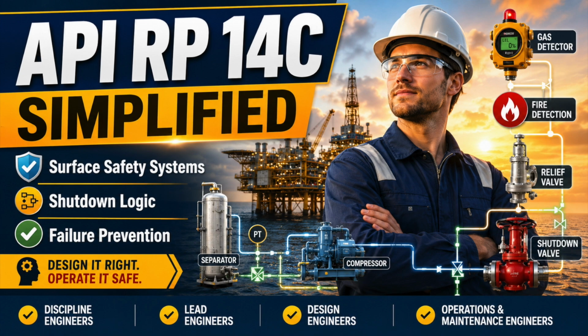One of the strongest design principles is the use of two protection levels that are independent of normal process control and, where practical, functionally different from one another. A pressure controller regulates normal operation. A high-pressure shutdown intervenes when control is no longer trustworthy. A pressure safety valve protects the equipment if the shutdown fails, responds too slowly, or cannot remove every pressure source. Those protections are not duplicates. They act differently. One removes the source, the other relieves the consequence. That is real defense in depth.